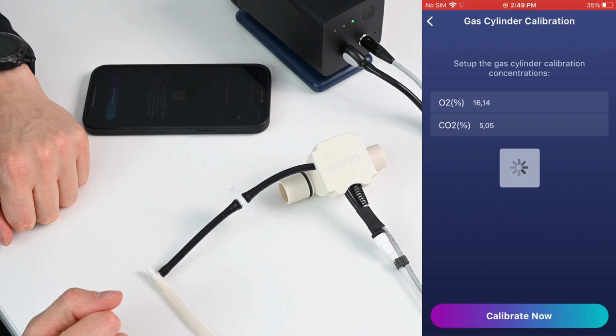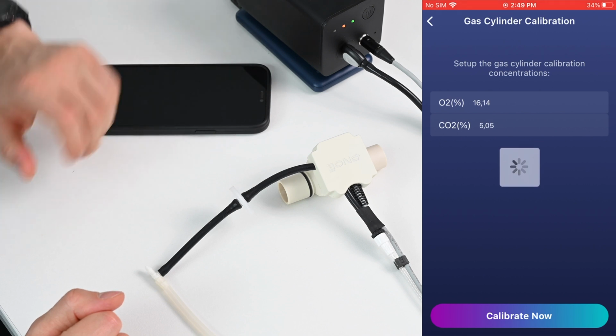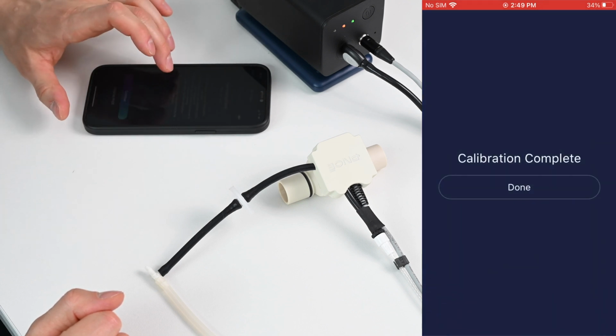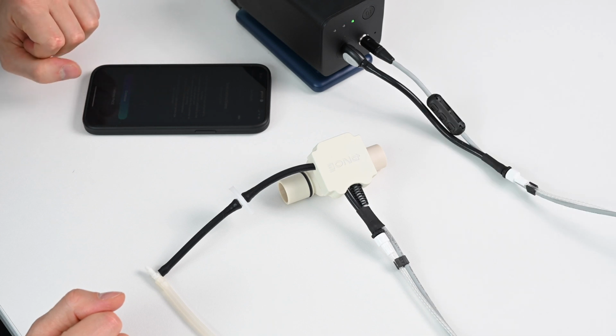From here, you will connect the gas line from your gas cylinder to the T connector on the one end. Then you will connect the sampling line of the flow sensor to the T connector's side port. After, you will turn the valve on your gas cylinder to charge its gas line, and perform the calibration. Even with a gas cylinder calibration, make sure to perform 2 consecutive calibrations prior to the test.